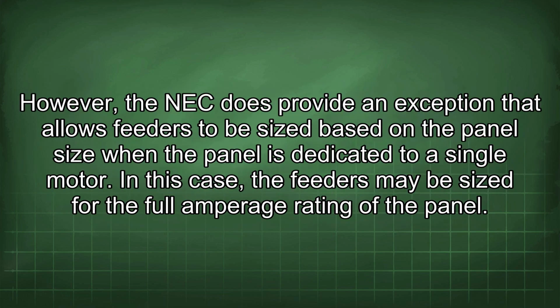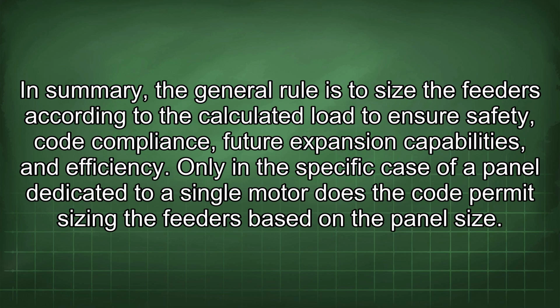However, the NEC does provide an exception that allows feeders to be sized based on the panel size when the panel is dedicated to a single motor. In this case, the feeders may be sized for the full amperage rating of the panel. In summary, the general rule is to size the feeders according to the calculated load to ensure safety, code compliance, future expansion capabilities, and efficiency. Only in the specific case of a panel dedicated to a single motor does the code permit sizing the feeders based on the panel size.